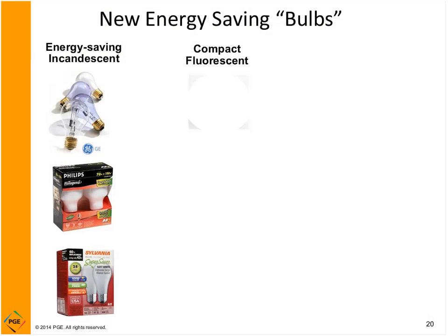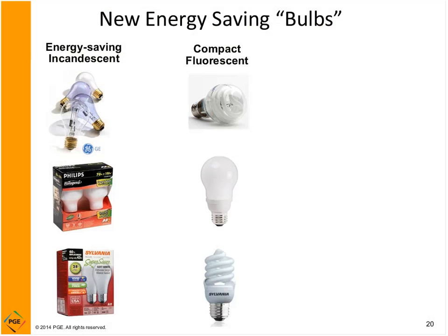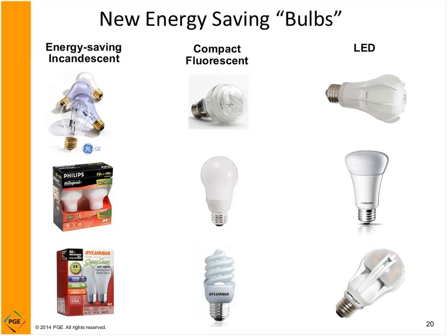Now CFLs are going to be better for applications that have longer hours of operation. You don't need to dim them, and there's infrequent switching, because switching is going to wear out compact fluorescent and linear fluorescent.